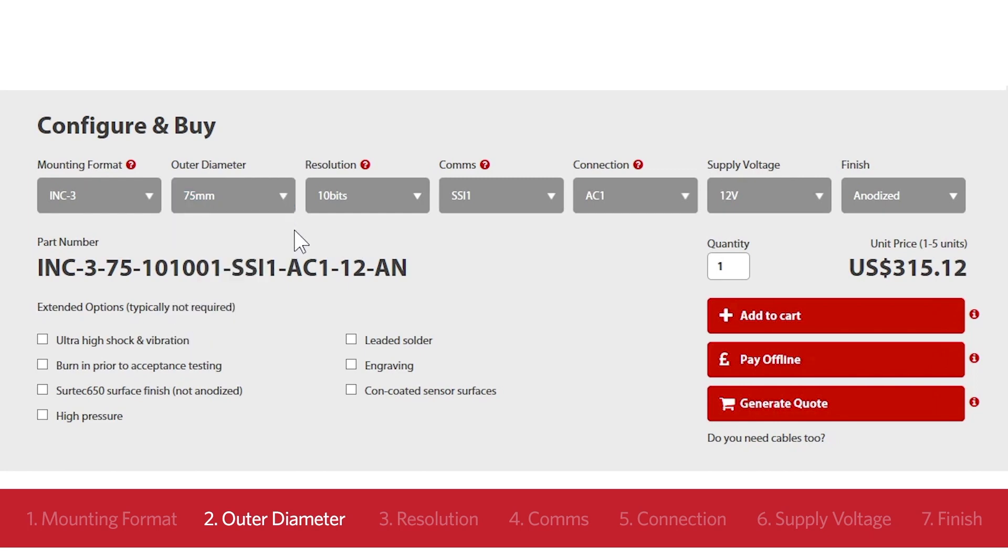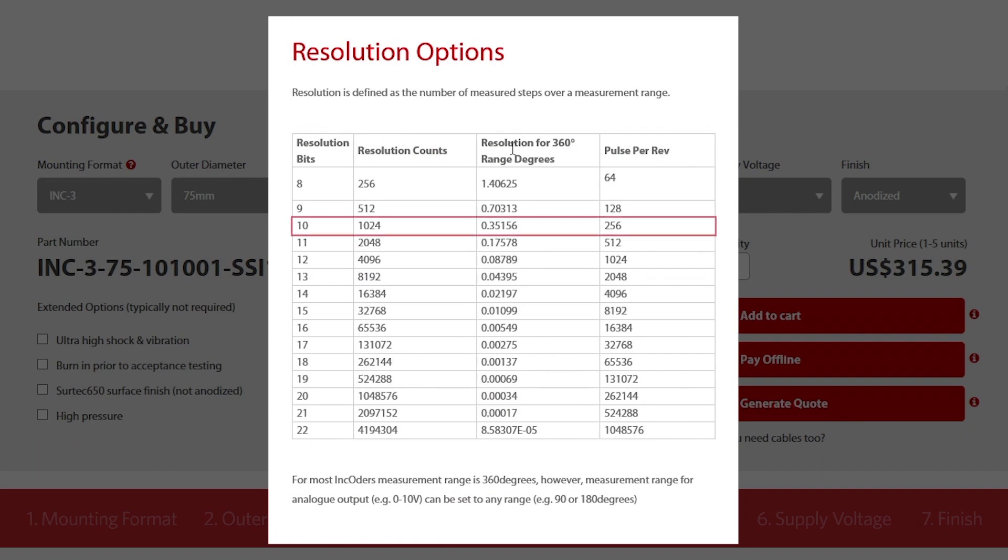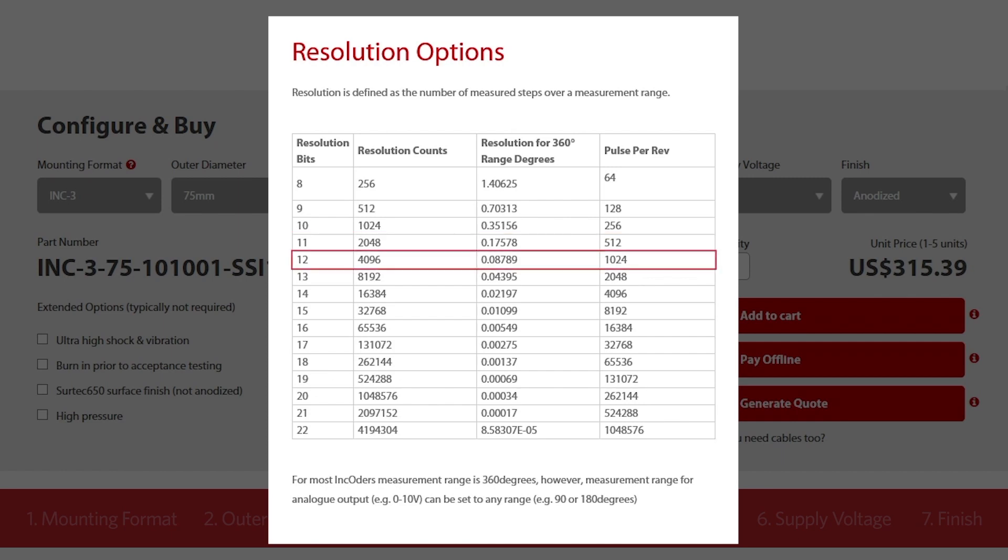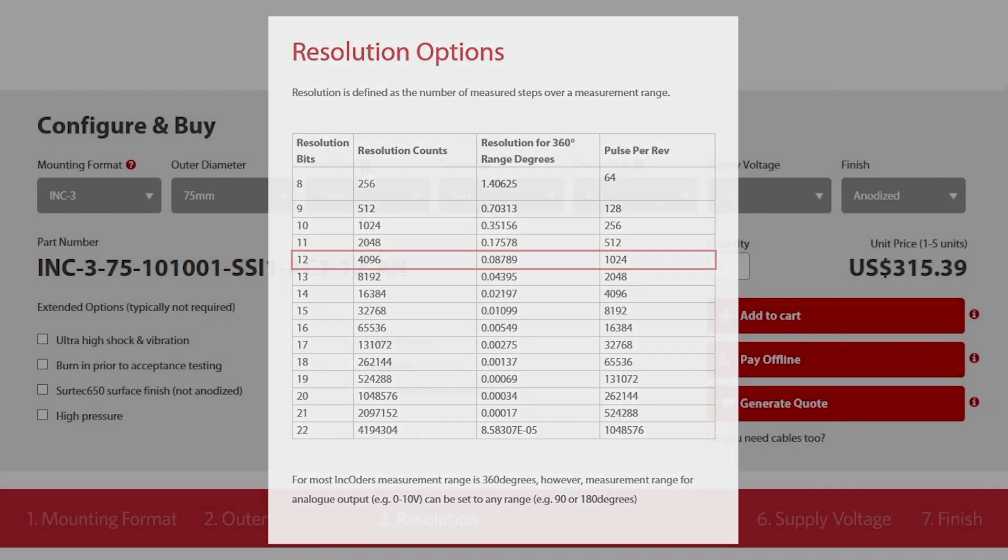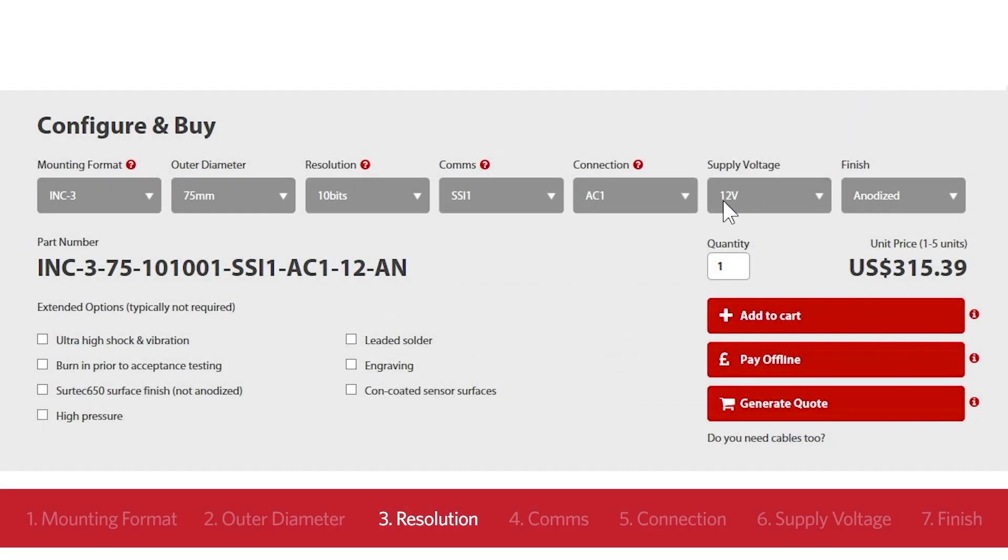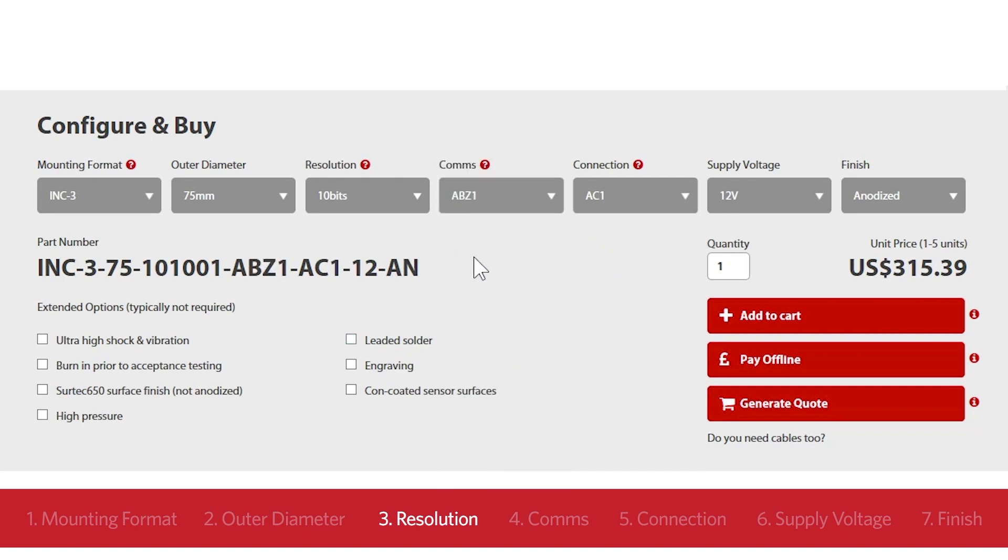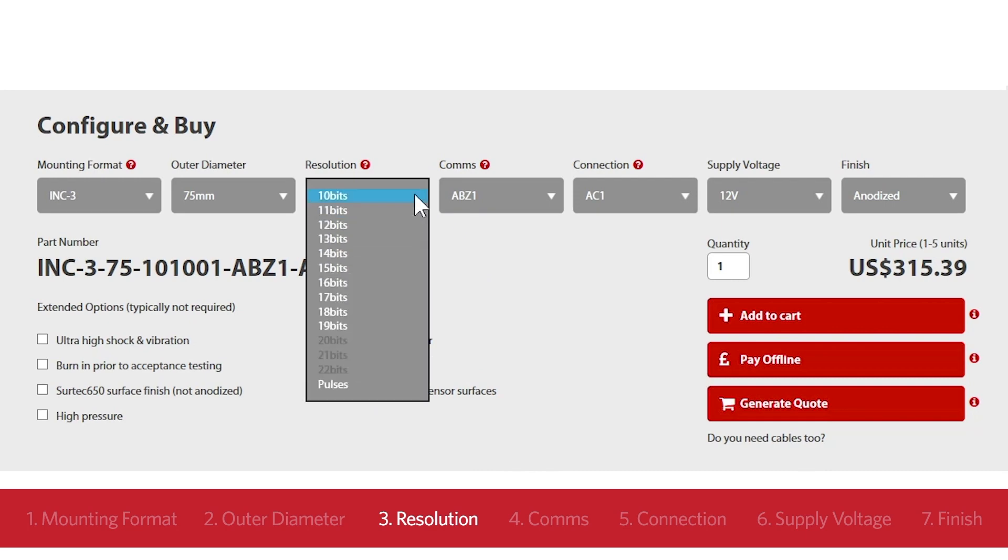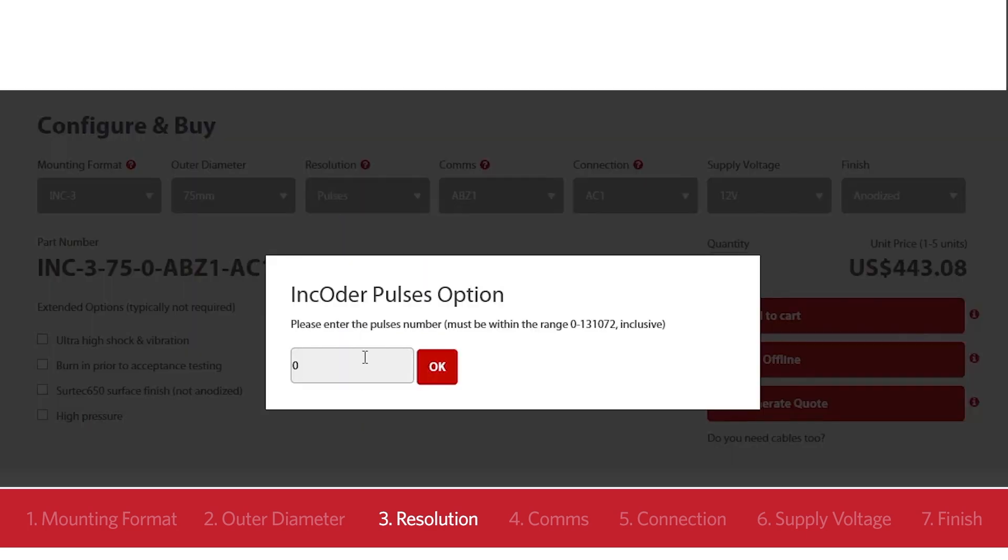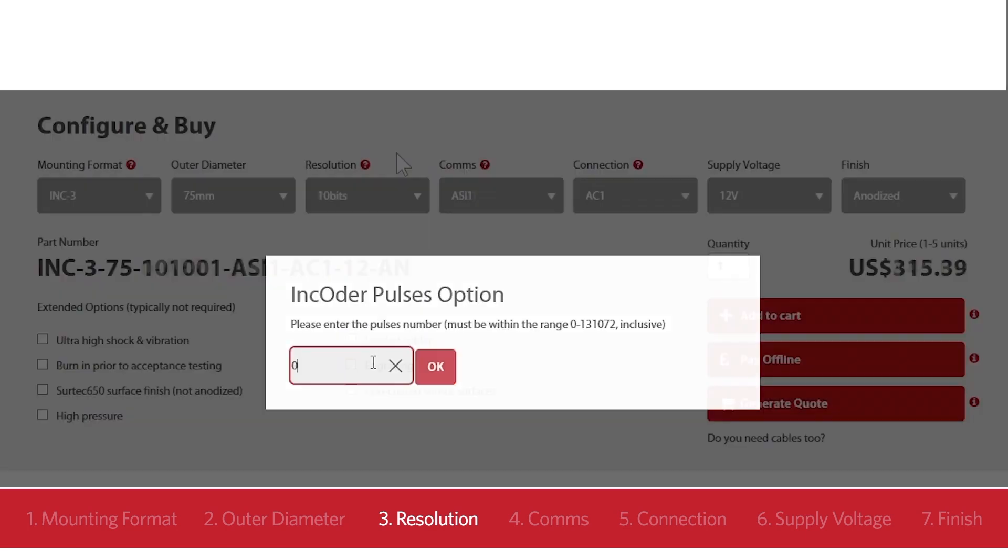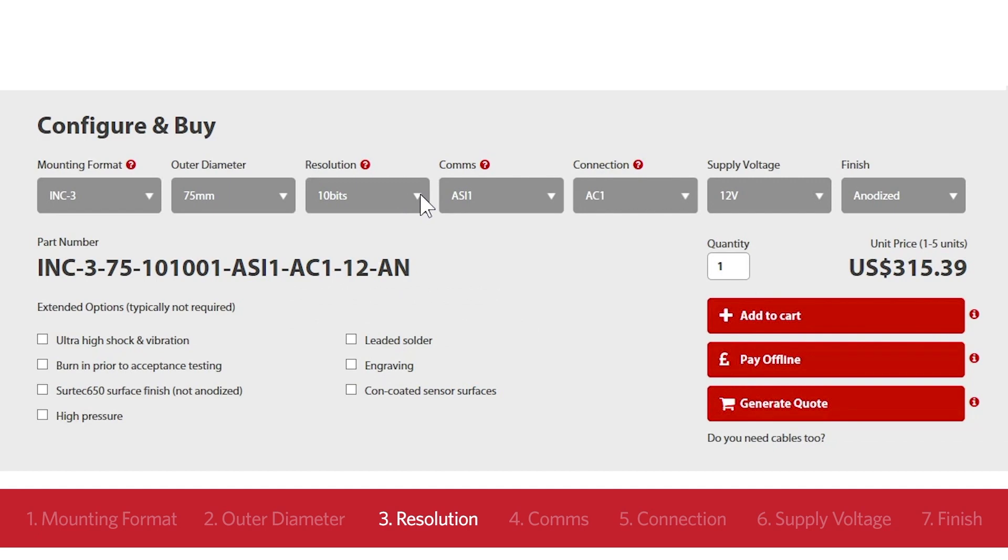The next element is resolution. Resolution refers to the number of measurement steps over one revolution. 10 bits refers to 1024 steps. 11 bits refers to twice as many, 2048. 12 bits is twice as many again, 4096 steps and so on. If you want the encoder to match an existing device with an AB pulse output, you can also specify the number of pulses per revolution. In our example, we're simply going to use 10 bits of resolution or 1024 steps.